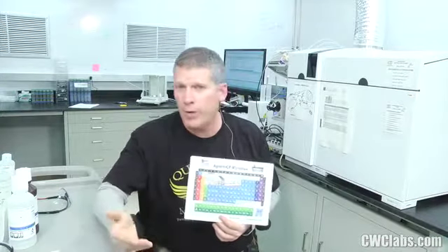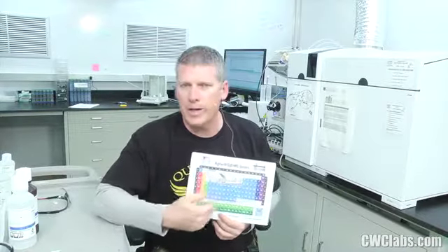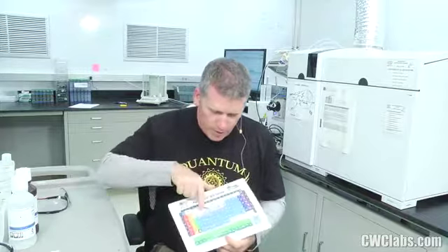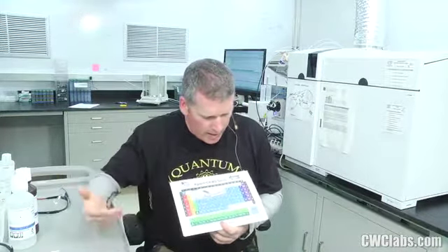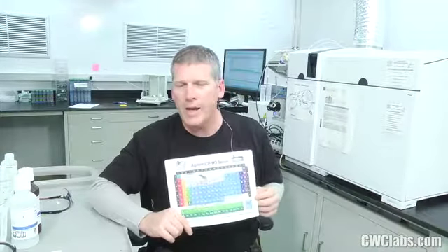So for example, you might have cadmium and lead and mercury looking fine, but you're having problems in a specific range like zinc and iron, for example, but not problems lower than that. You might only be having problems in a specific mass range, just this area here, maybe manganese, copper, zinc, and nickel, for example. Well, that's your clue right there. What it means is something's screwed up with your internal standard.